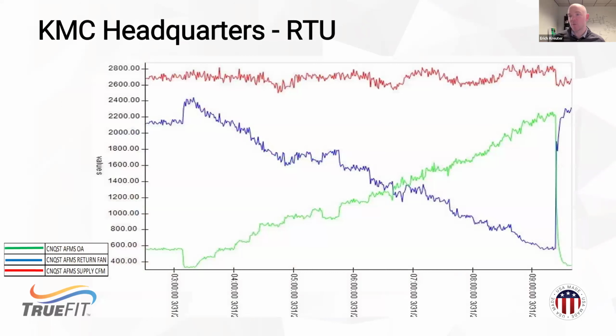And again, at the end of the day, as we modulate that damper from min to max, we see that the OA goes down, the return goes up, and those two always will add up to the proper supply number. So all of these measurements are coming out of that one airflow measurement system that we put in.